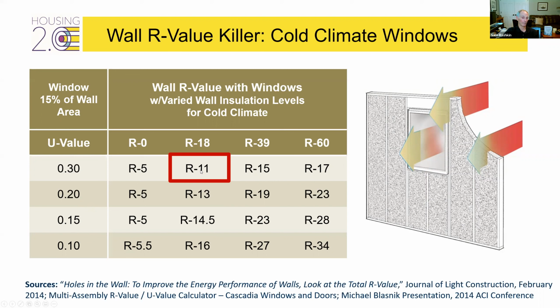That's significant, but that's just a 6-inch wall. If I have a 13-inch wall at R39, it's reduced by about 60% down to R15 with an Energy Star window. So I'm paying for all that - the thicker walls, extra framing and insulation to get the R39 wall - and if you don't have a high performance window, you've negated most of the benefit.